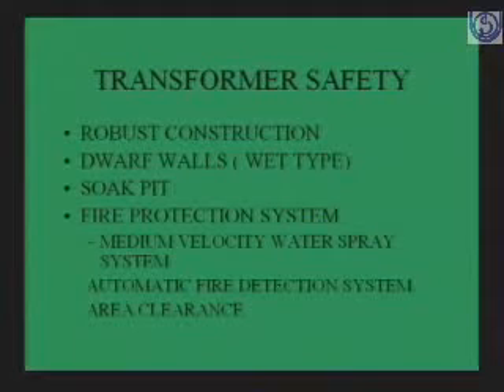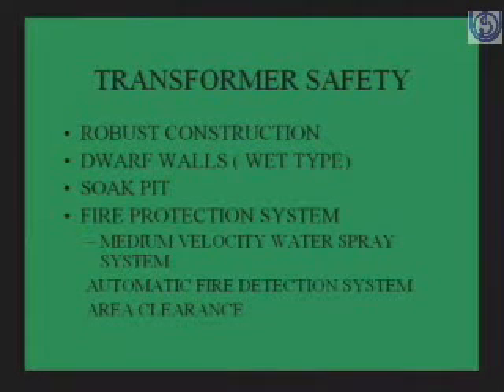Water is not reaching that particular place because before reaching the area, the radiated heat causes the water to evaporate. For that purpose, medium velocity or high velocity water spray systems are used. This is done in conjunction with an automatic detection system, because people are not always available near the transformers to actuate the fire protection system.